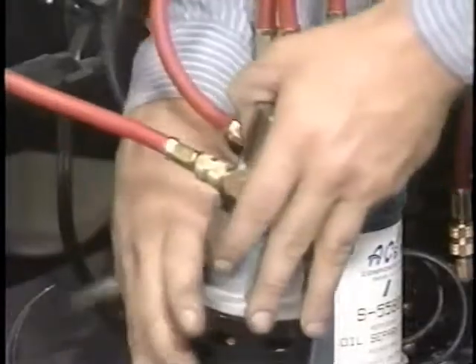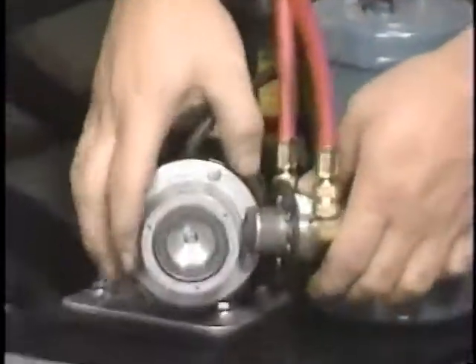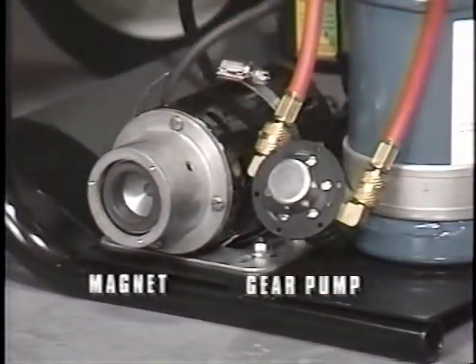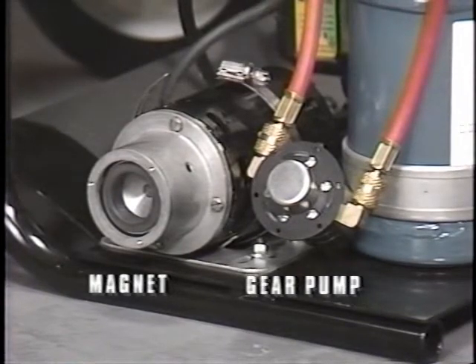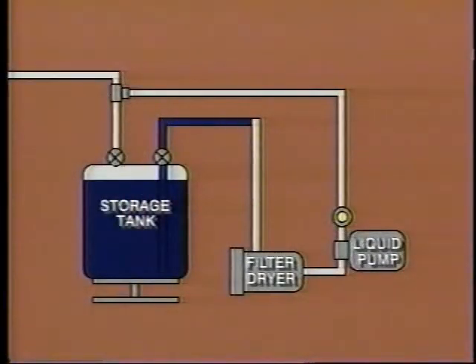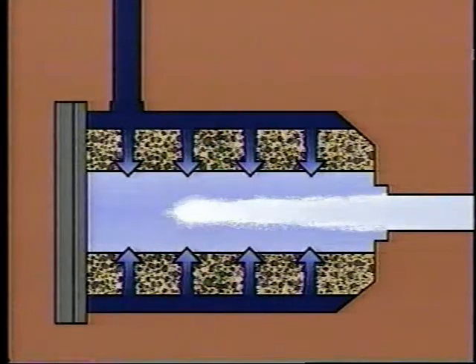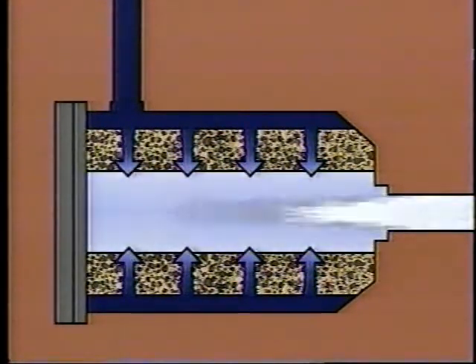A special pump moves the liquid R12 through the system. A powerful magnet spins the gear pump. See? No shaft. This eliminates heat transfer so that the R12 doesn't flash in the pump's gears. The pump draws liquid R12 from the refillable storage tank and into the filter dryer core. The filter dryer core traps all moisture and contaminants and separates oil from the liquid refrigerant.